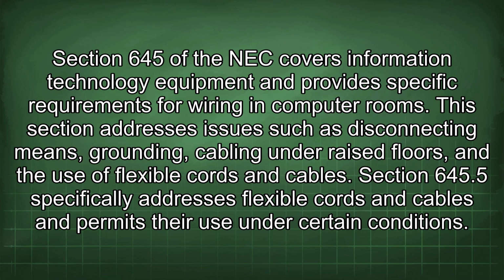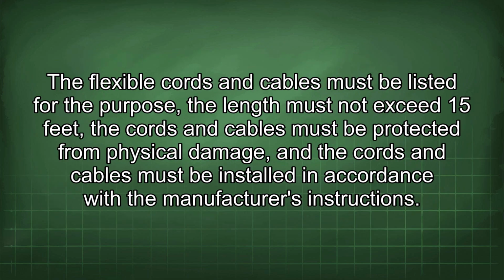Section 645.5 specifically addresses flexible cords and cables and permits their use under certain conditions. The flexible cords and cables must be listed for the purpose, the length must not exceed 15 feet, the cords and cables must be protected from physical damage, and the cords and cables must be installed in accordance with the manufacturer's instructions.